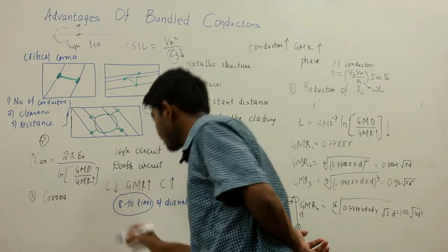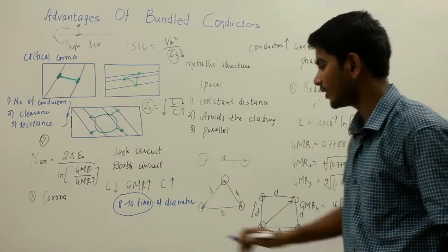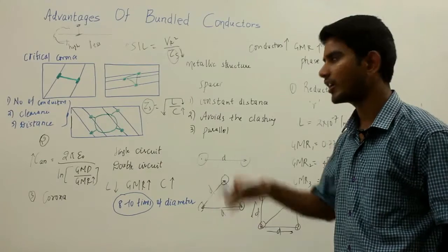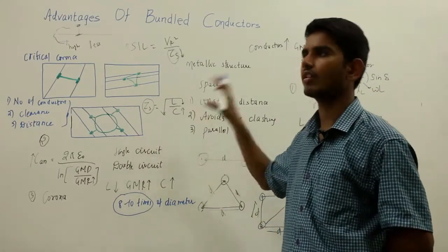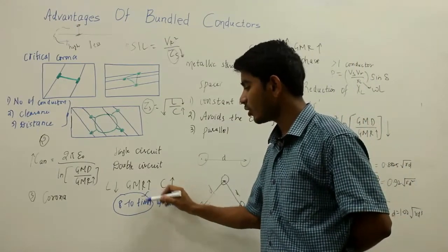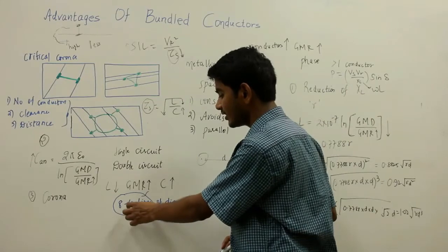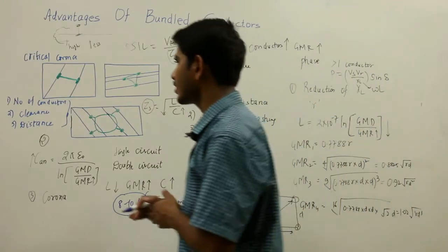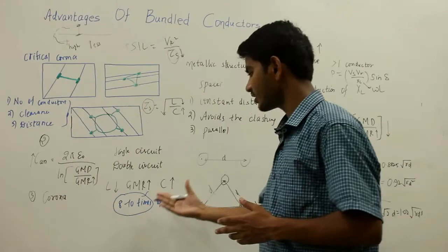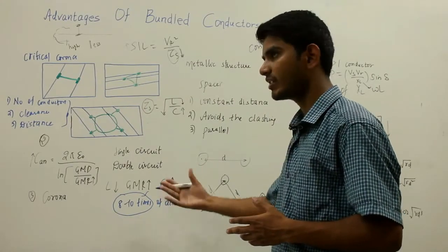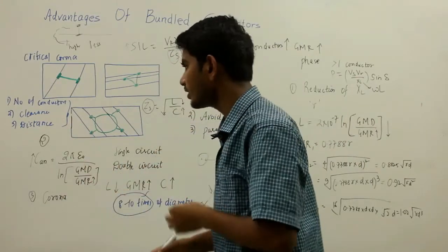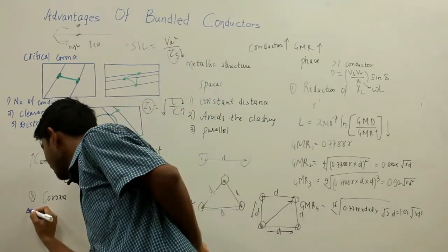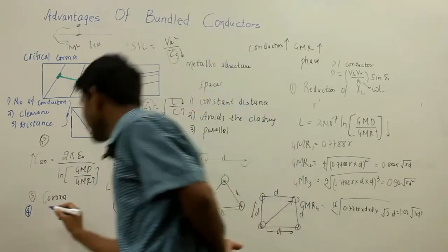It has been found that the spacing between the conductors in a group is of the order of 8 to 10 times the diameter of each conductor, irrespective of the conductors being used. Whatever conductor you use, whether 5 or 6 or 7 or 8, the spacing is optimum when the distance is 8 to 10 times the diameter of each conductor. So you can increase your critical corona voltage by employing more conductors, with this spacing of 8 to 10 times the diameter, and more distance between two groups forming separate phases.